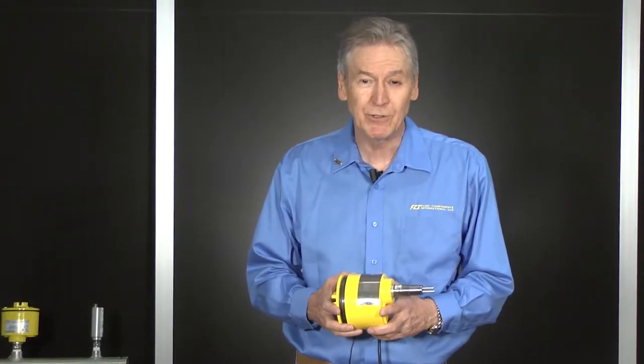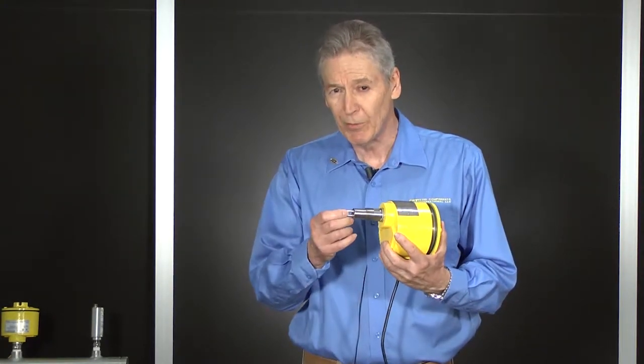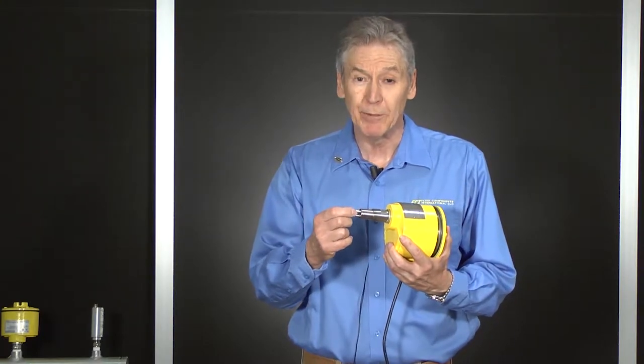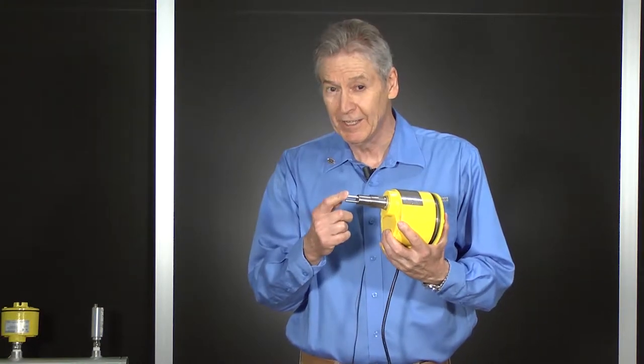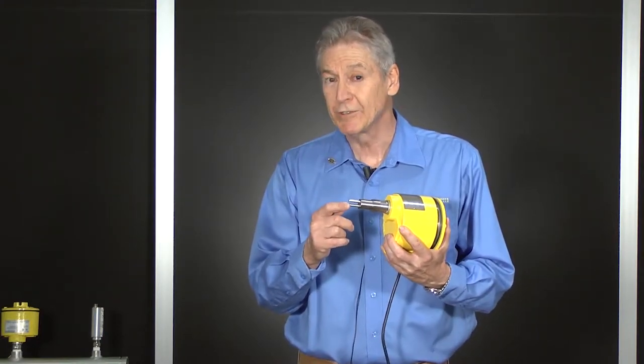The FLT-93 is a flow, level, and temperature switch that uses a thermal dispersion principle of operation. The sensor element has two thermal wells, each containing a platinum resistor temperature detector, or RTD. One of the RTDs is heated, the other RTD is left unheated as a reference. This creates a difference in temperature between the two RTDs that varies with the flow velocity and the thermal conductivity of the process fluid.